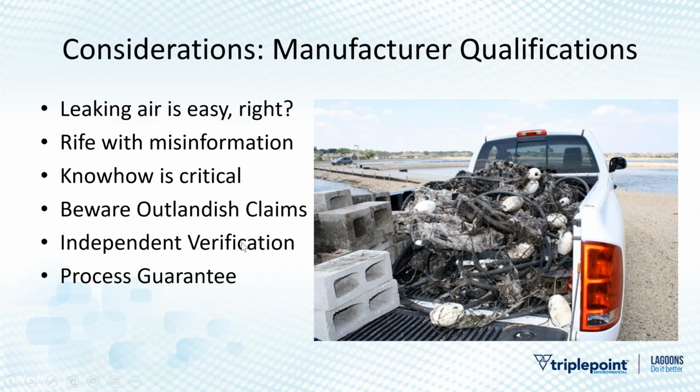And the whole lagoon aeration market is kind of rife with misinformation. So you have to be judicious and really make sure you're going through the details on people's aeration calculations, and is their SOTE reasonable? Is their alpha appropriate for this kind of technology in this basin? So you've got to arm yourself a little bit, and you want to beware of outlandish claims.